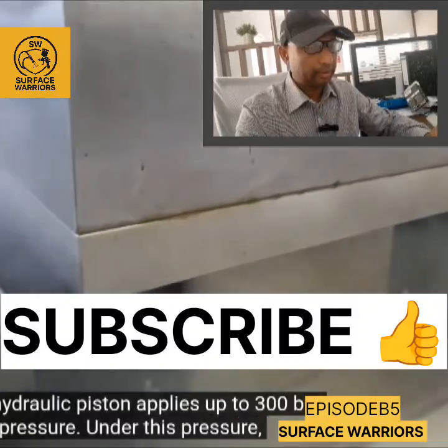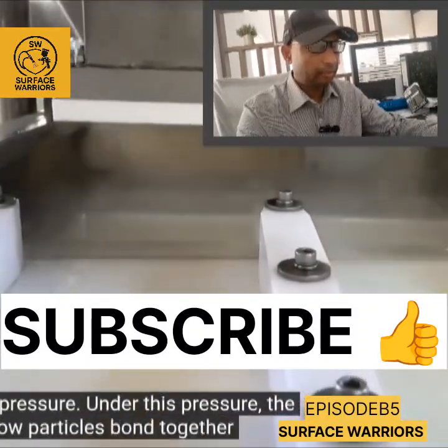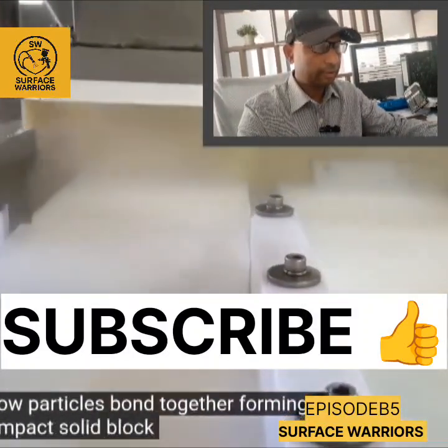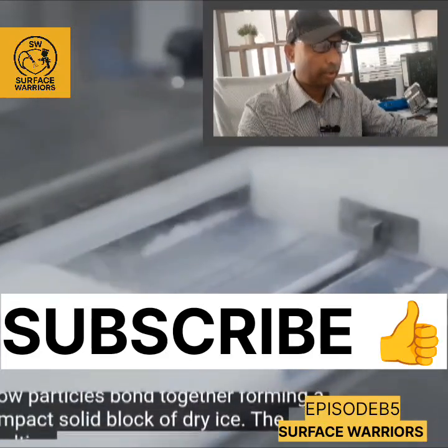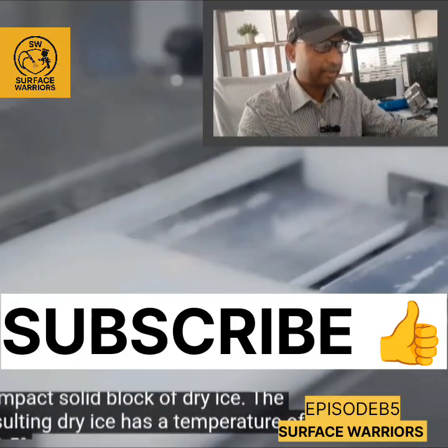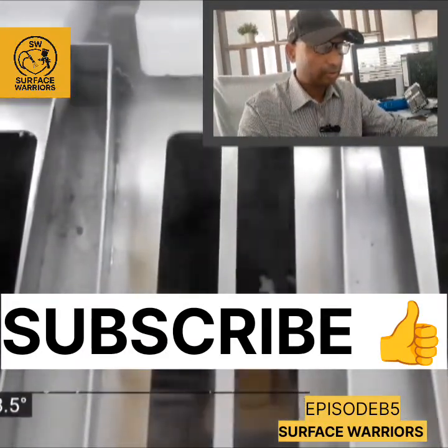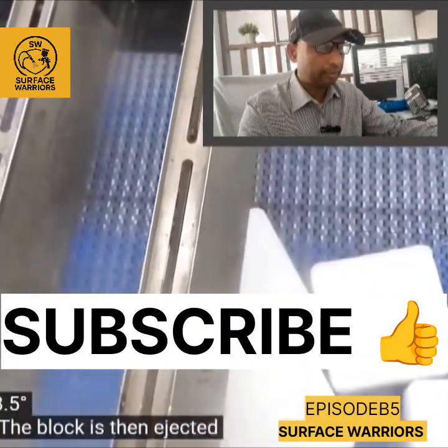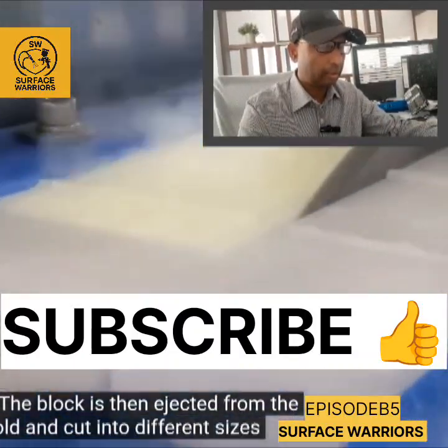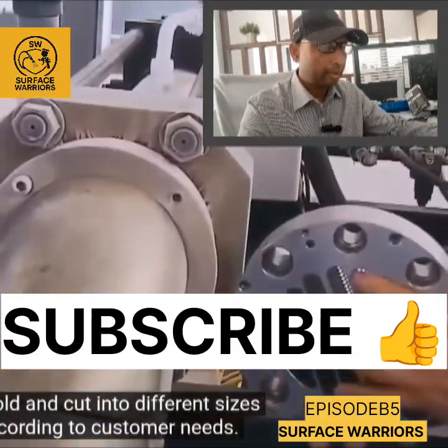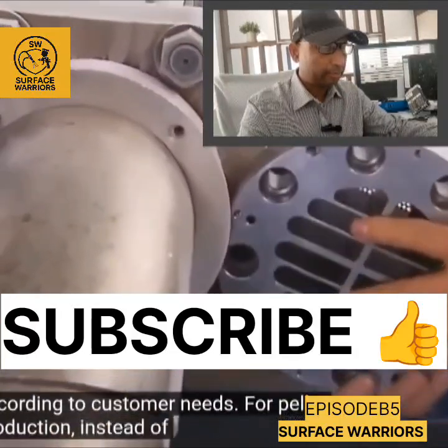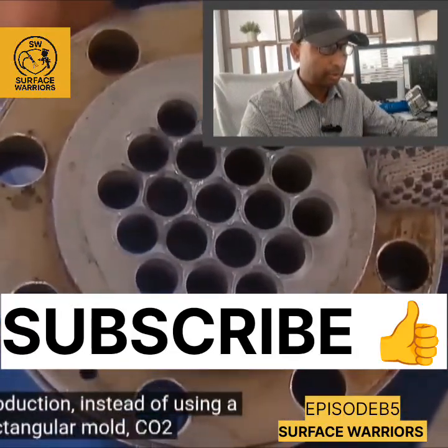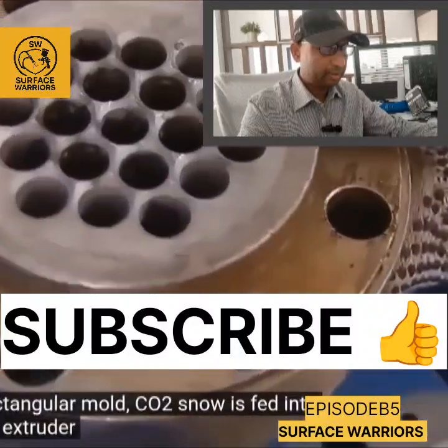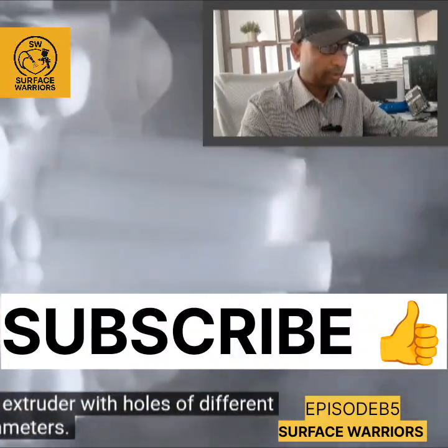For pellet production, instead of using a rectangular mold, carbon dioxide snow is fed into an extruder with holes of different diameters. A mechanical piston pushes the snow through the holes with great force, forming solid dry ice cylinders. Depending on the hole diameter, large 16 mm pellets can be produced for refrigeration and transport. The plant here also manufactures 3 mm pellets used for cryogenic cleaning.